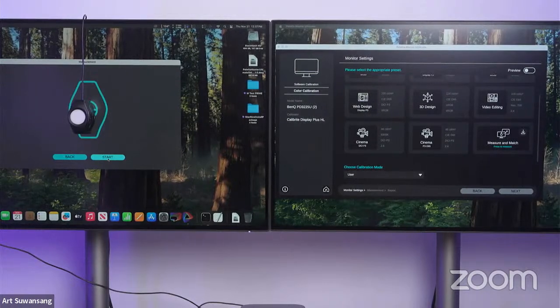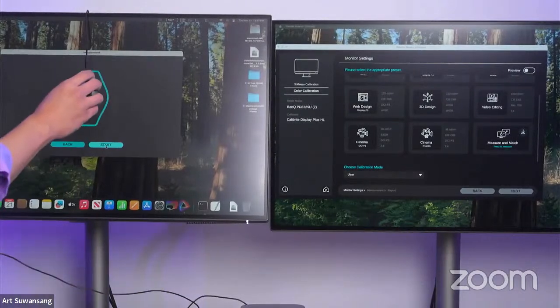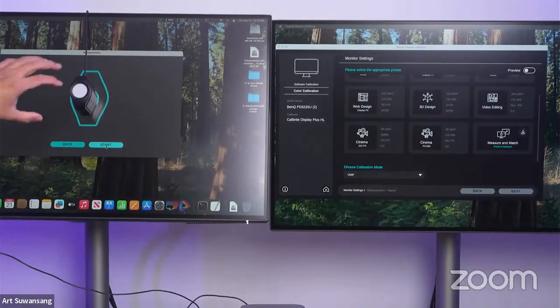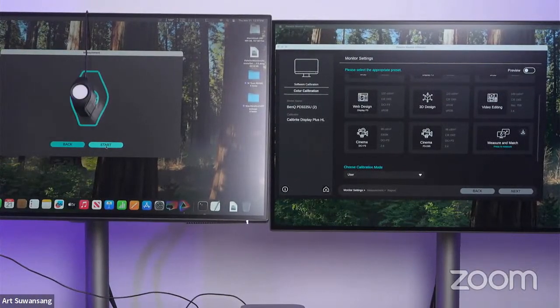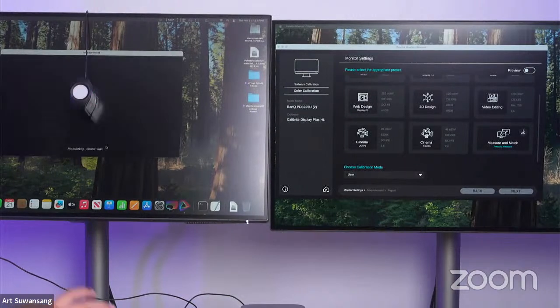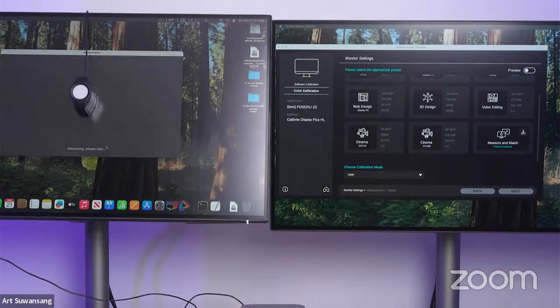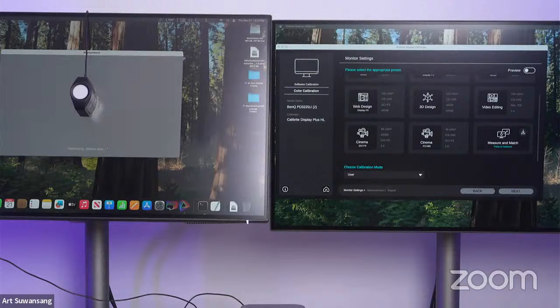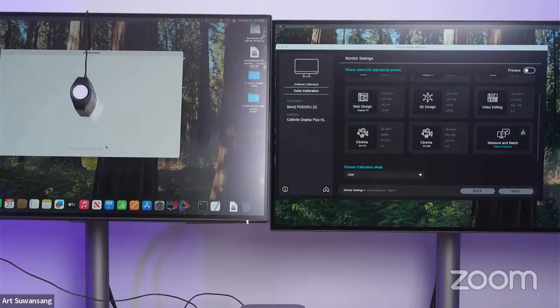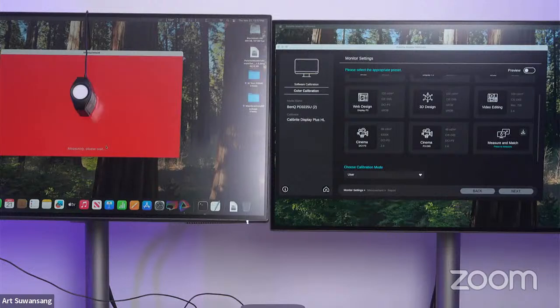And I'm going to click on next, align this up. With that, tilt the display back. Make sure that you do tilt the display back. Otherwise, your device may not sit fully flat on the display and that can change the result. I'm going to click on start and it's going to do the measurement. So what it's doing right now is measuring all these known values that it's going to do the adjustment for. And it's going to give me a report of how this display is outputting color. So we're going to give this a moment.